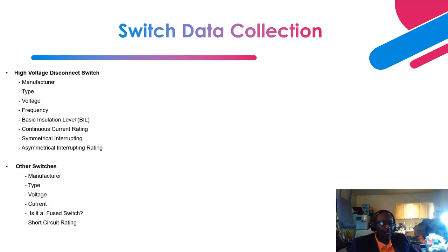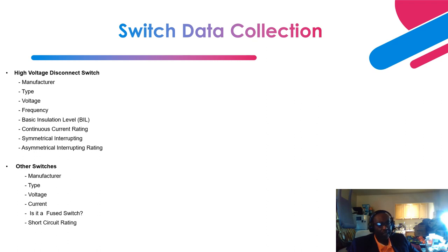For high voltage disconnect switches — which include vertical break, center-pivot, and double break types — you need the manufacturer, type, voltage, frequency, basic insulation level, continuous current rating, symmetrical rating, and asymmetrical rating. For other switches, you need the manufacturer, type, voltage, current, whether it is a fused switch, and the short circuit rating.